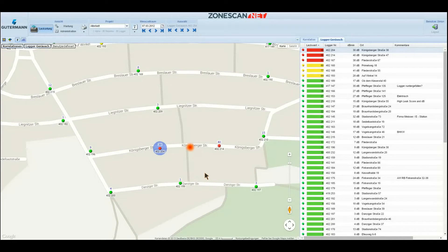The ZoneScan system does not only provide histograms and the spectrum for each measurement point, but it also records and collects several sound samples from every logger every single night. These sound recordings are synchronized to the millisecond, which enables the system to correlate and compare all logger sound recordings and determine whether and which two loggers are picking up the exact same noise source.